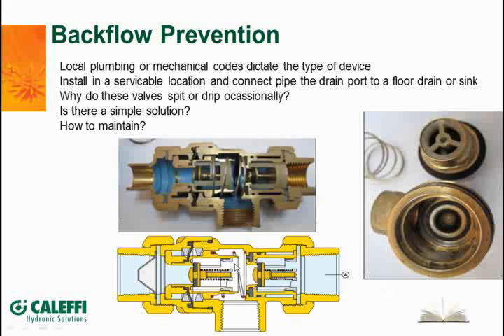But this here, again, is the problem area, and that's where the drips are going to be caused, because it's coming through here and it's leaking down through this little seal right here. So what you can do on this valve and pretty much any valve out there, you can actually disassemble them right here with the channel locks and take it apart, and you can just pull this back and reach up in there and take the spool right out, or sometimes you can just reach in there.